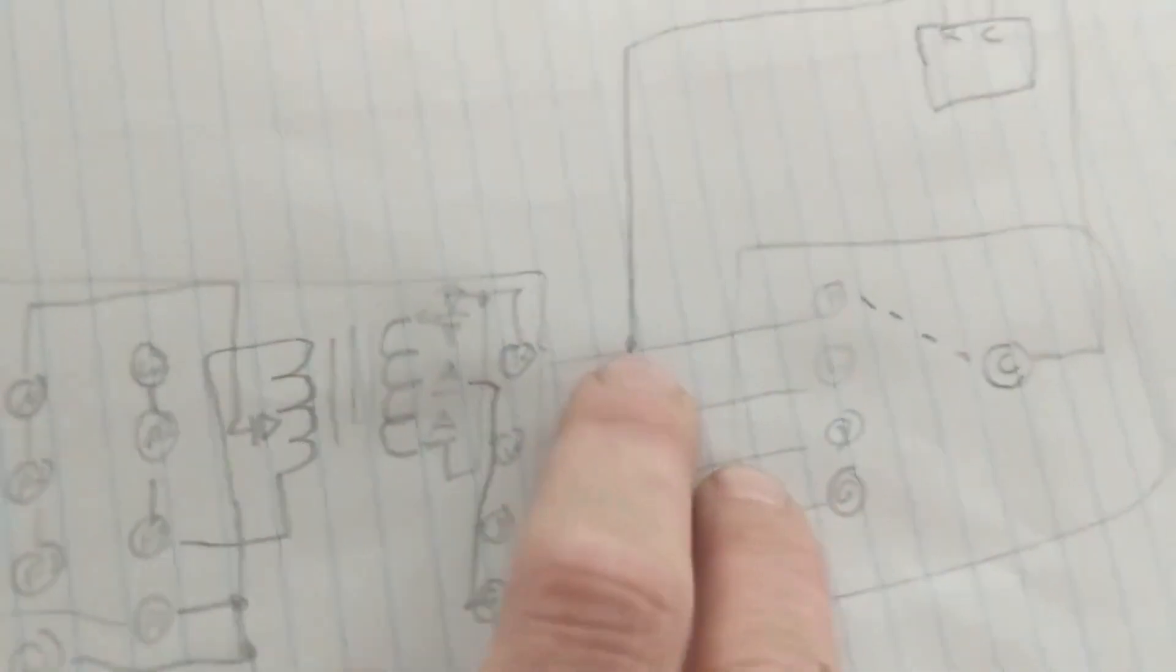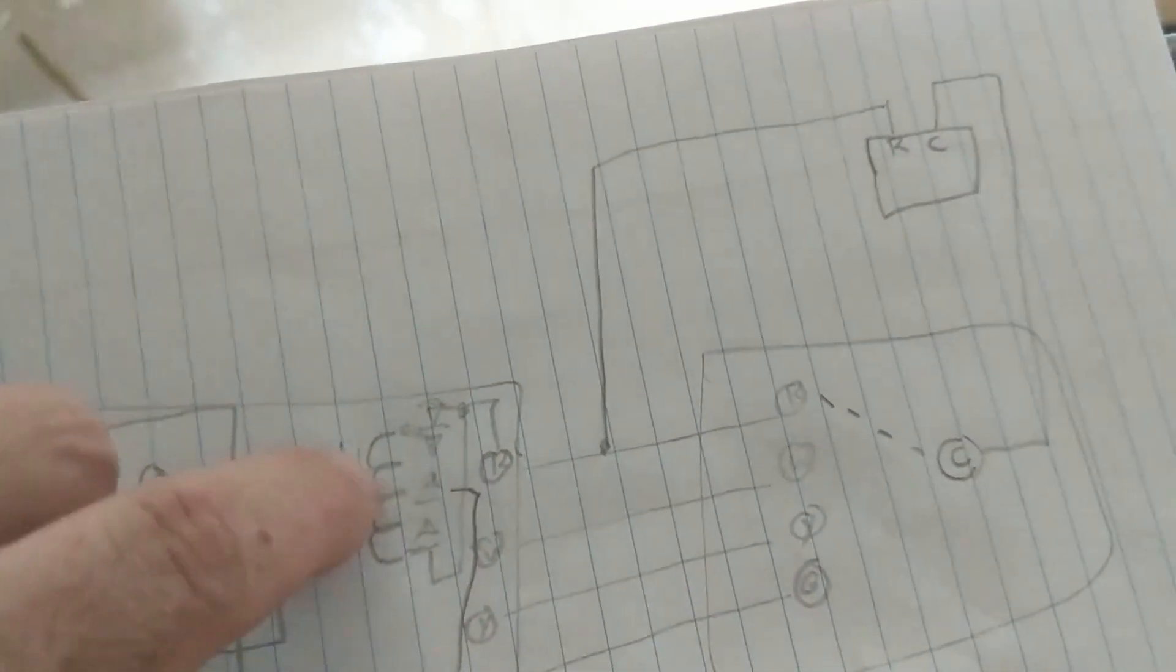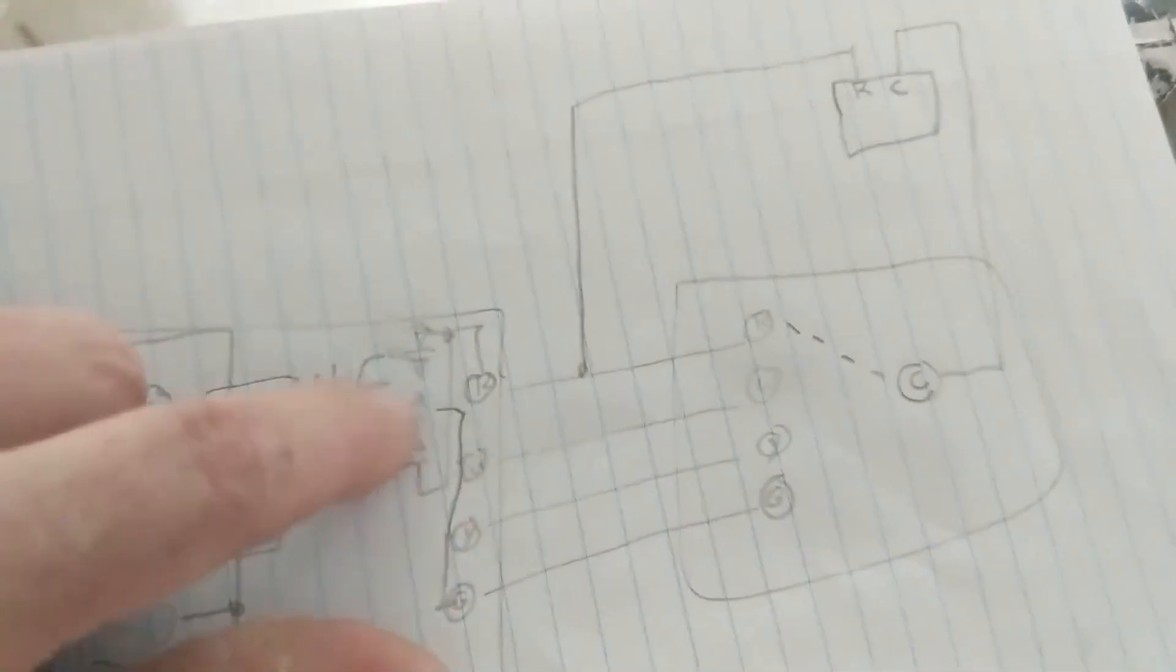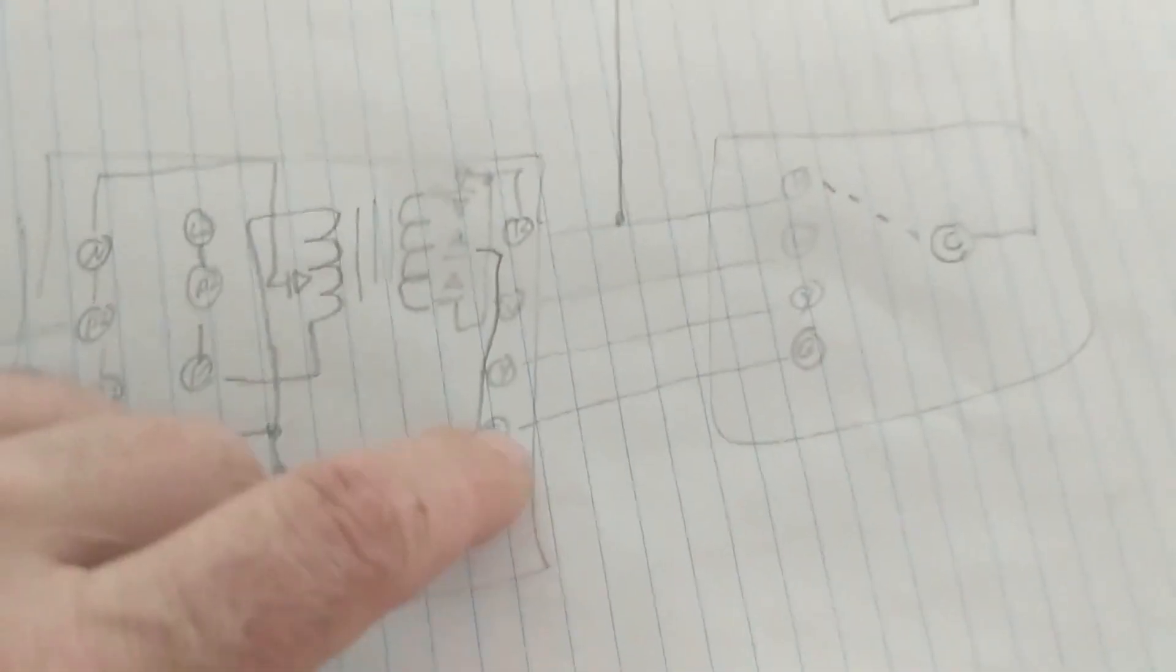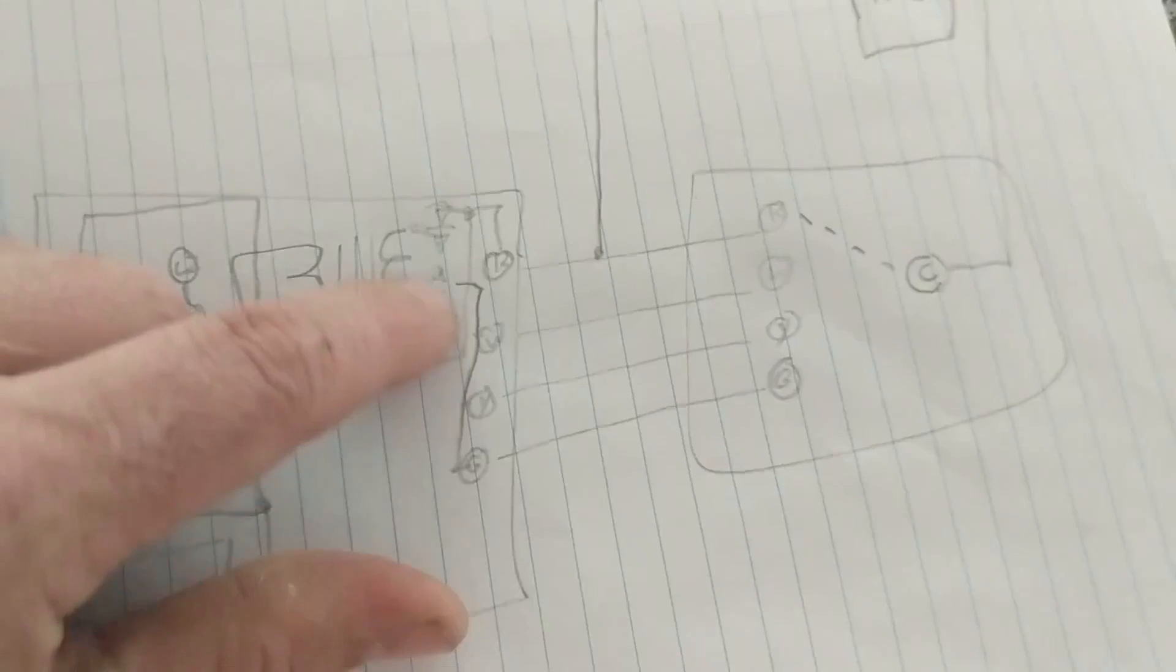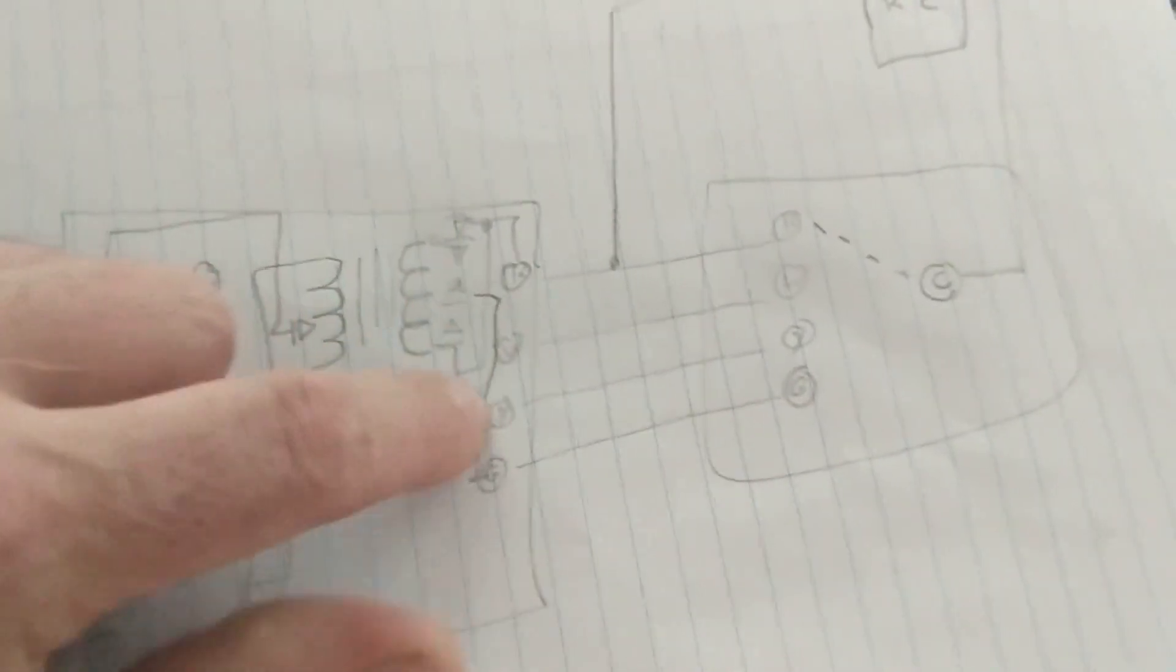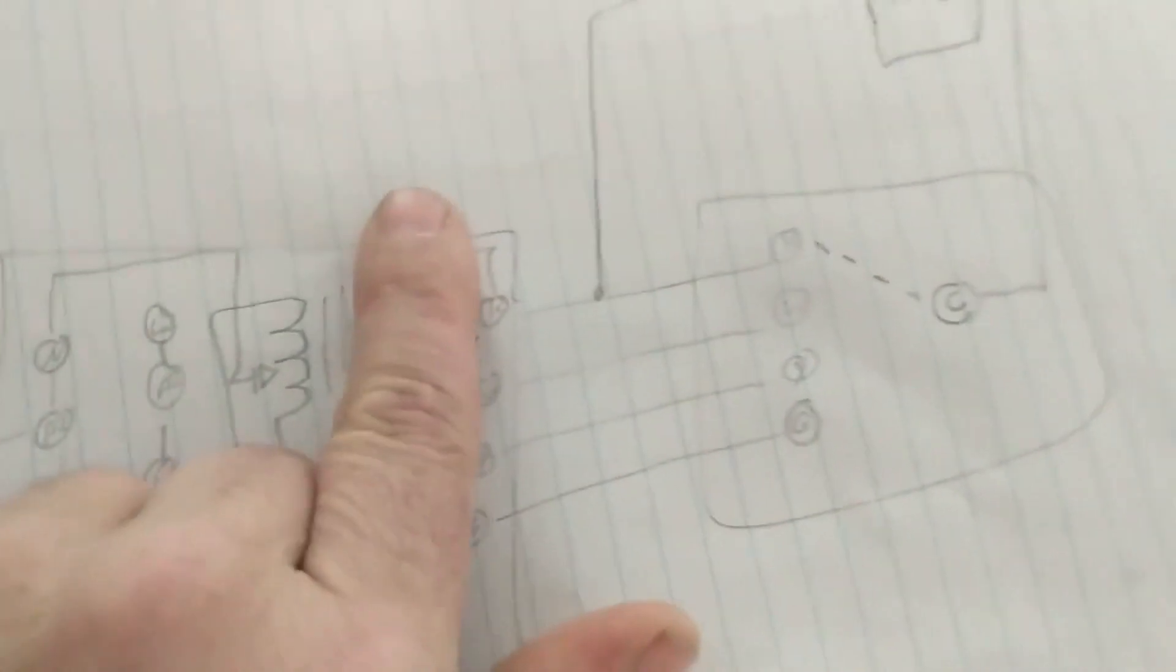It doesn't technically need a common wire - any of these can run this circuit. If you were to twist these together, they'll run, so this isn't necessary. If you needed a common wire, this is an easy simple solution to do so. Cool thing about this is it's not going to fry it - you've got power running across here, this is a good consumer, and these are diodes so the power can't backfeed into this system. You've already got continuous power through this entire thing. The whole relay is being pulled, clicks, closes, makes contact, and then the power comes through this thing and runs up through these diodes into the center power here and runs down through these wires depending on what leg you're looking on.